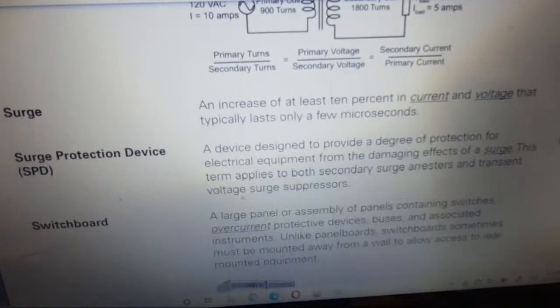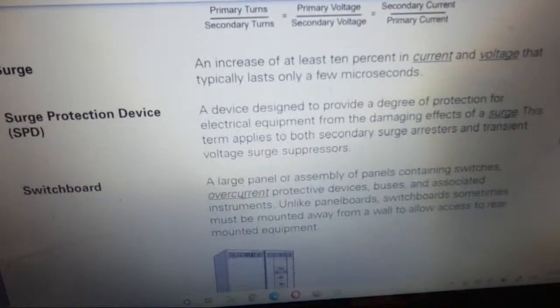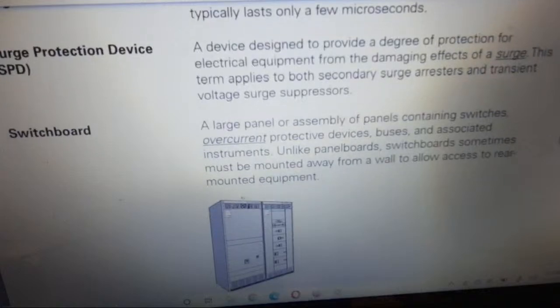Surge, an increase of at least 10% in current or voltage that typically lasts only a few microseconds. Surge protection device, a device designed to provide a degree of protection for electrical equipment from the damaging effects of surges. This term applies to both secondary surge arresters and transient voltage surge suppressors. Switchboard, a large panel or assembly of panels containing switches, overcurrent protective devices, buses, and associated instruments. Unlike a panelboard, a switchboard sometimes must be mounted away from the wall to allow access to rear mounted equipment.